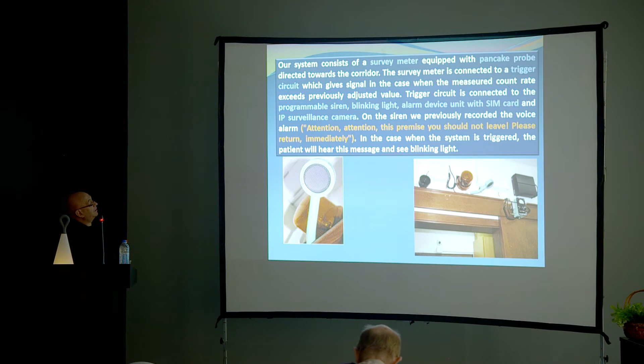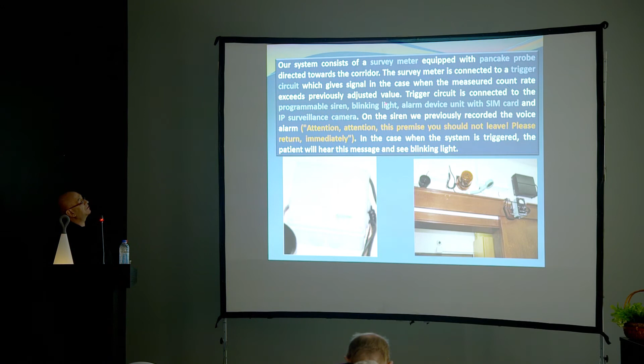Our system consists of a survey meter equipped with a pancake probe which is directed towards the corridor. The survey meter is connected to a trigger circuit which gives a signal in the case when the measured count rate exceeds a previously adjusted value. The trigger circuit is connected to a programmable siren, blinking light, and an alarm device unit which is able to call mobile or fixed phones. Also, it is connected to an IP surveillance camera.